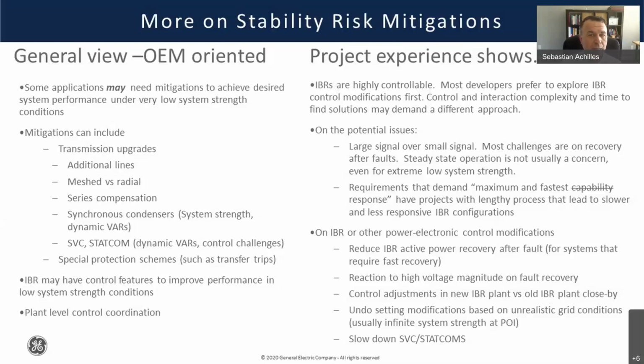Regarding the potential issues that we see, there's this discussion about large signal versus small signal. There's this aspect of weak grid that has to do with small signal, that if you have a very weak condition, you look at, for example, the synchronization problem that Nick was describing, and make sure that for small variations, the PLL is able to track the voltage variation quickly enough that the injection of active and reactive current makes the system stable. That aspect, with small variations, is in fairly good shape. Typically, those are not the problems that we see.